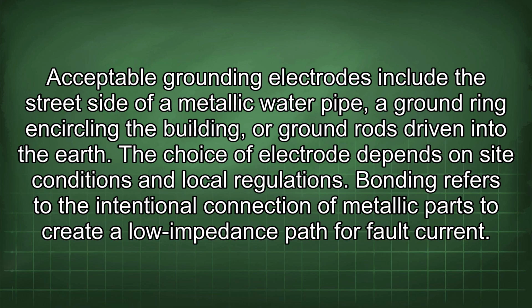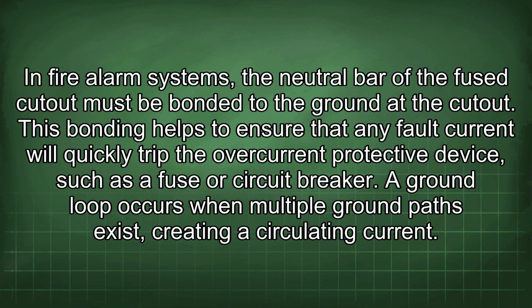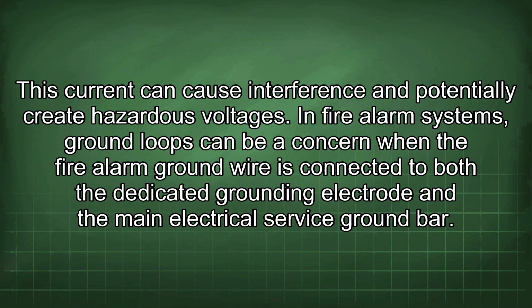Bonding refers to the intentional connection of metallic parts to create a low impedance path for fault current. In fire alarm systems, the neutral bar of the fuse cutout must be bonded to the ground at the cutout. This bonding helps to ensure that any fault current will quickly trip the overcurrent protective device, such as a fuse or circuit breaker. A ground loop occurs when multiple ground paths exist, creating a circulating current. This current can cause interference and potentially create hazardous voltages.